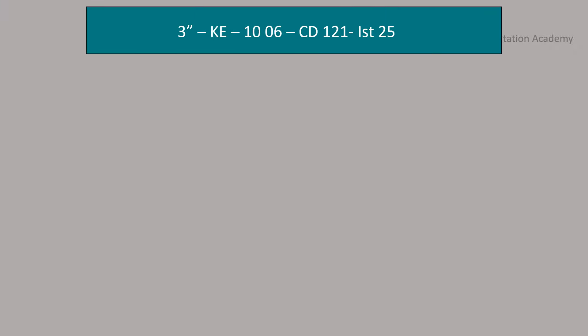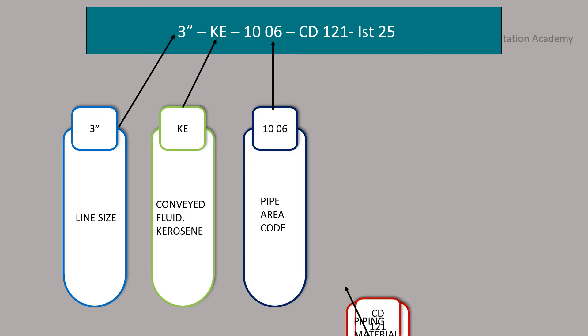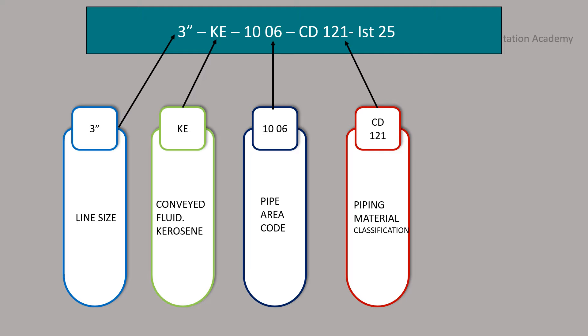Now let's see an example of line number. In this line number, three represents line size. KE represents conveyed fluid. 1006 represents area code. CD121 represents piping material classification and the last part represents insulation type and size.